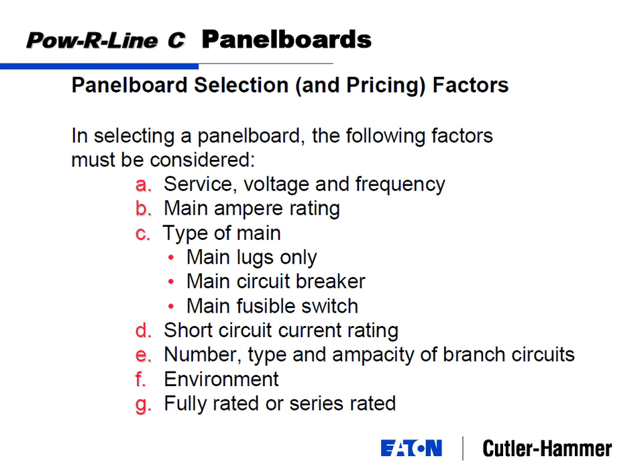Service meaning delta or Y, voltage 480, 277, or 208, and frequency. And of course, if you're in North America, we're 60 hertz. But if you go overseas, you might be 50 hertz. If you go down to the ground, the airport runway, you're going to be at 400 hertz. So there's a couple of oddballs, but basically 60 hertz covers us in North America here. Your ampere rating, the type of main, whether it's main lugs, circuit breaker, or main fuses. The short circuit current rating, the maximum available fault current at that device itself. And then you look at your branch circuits, the number of branch circuits, type, and the ampacity of each individual branch circuit.